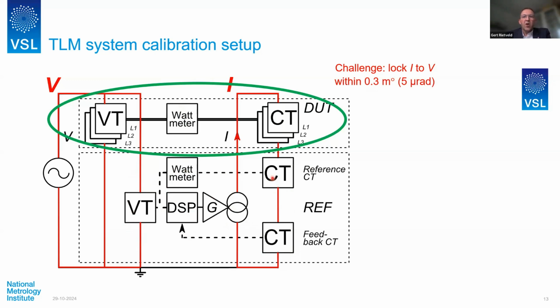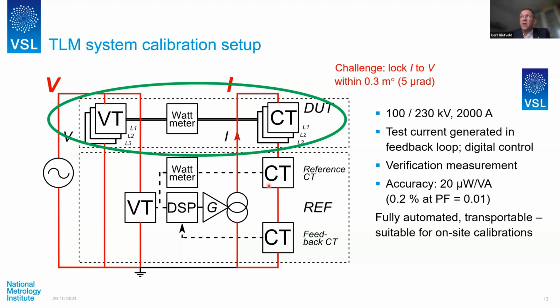It's an indicator for us, doing the calibration, to what extent our reference system is really consistent and giving highly accurate results. So the range of the system is 100 to 230 kV, 2000 amps. I already mentioned the key part of our system is the digital signal processing. That's the heart of the setup. That's where all the intelligence is. Really difficult to completely develop. But then by calibrating all the components and by getting low noise through the digital signal processing, we were able to presently achieve 20 microwatt per VA, 0.2% at power factor 0.01.